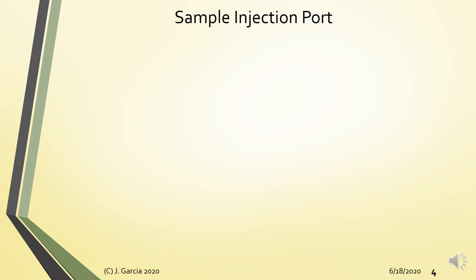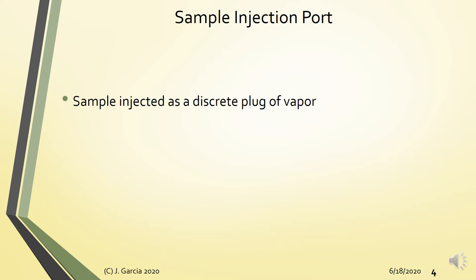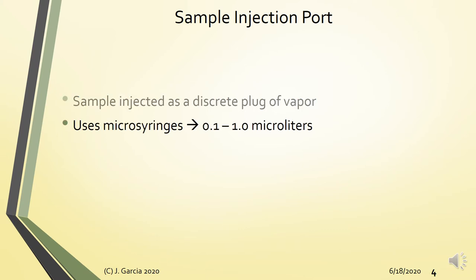In gas chromatography, the sample is injected as a discrete plug of vapor. You can inject your sample either as a gas or as a liquid, because the temperature of the sample injection port is elevated enough that even a liquid sample will be vaporized. To introduce the sample, you need a microsyringe. For liquid samples, typical volumes are 0.1 to 1 microliter, normally made from glass with a stainless steel plunger.